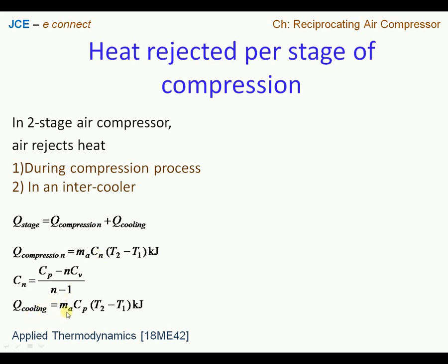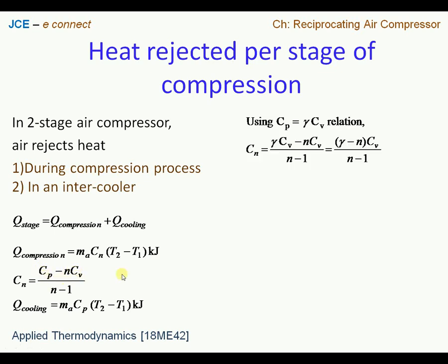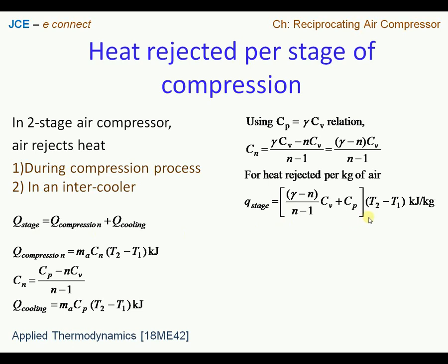For the heat rejected during cooling, one can write mass flow rate of air times cp times the change in temperature. Using the relation cp/cv = γ, one can modify the cn relation so that cn takes the final form (γ − n)·cv / (n − 1). Plugging in both the heat transfer due to compression and heat transfer due to cooling, we get the total heat rejected per stage.